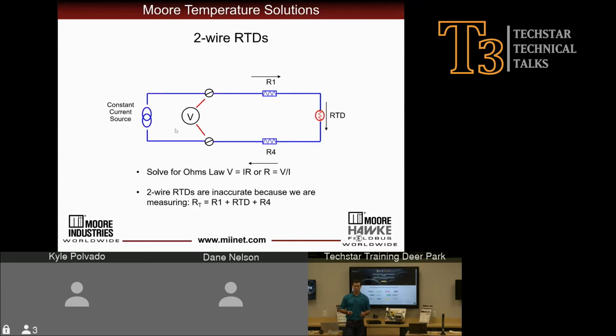With a 2-wire RTD, what we're effectively doing is running a voltmeter across an RTD element. We're measuring that resistance and solving for Ohm's law with our voltmeter, and that effectively gives us what our temperature is. Now with the 2-wire RTD, we're passing a constant current source over this RTD so that we're able to solve for Ohm's law. If we're trying to get voltage, we need current and a resistance, and if we're trying to solve for resistance, then we'll take the voltage over our known current.